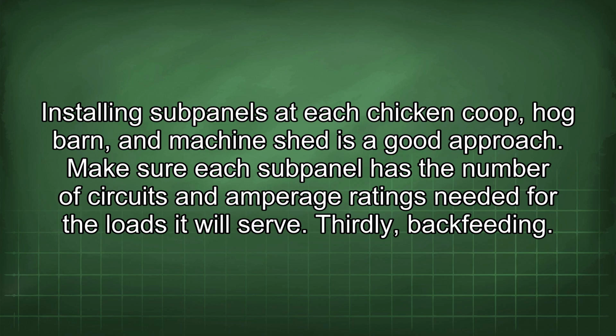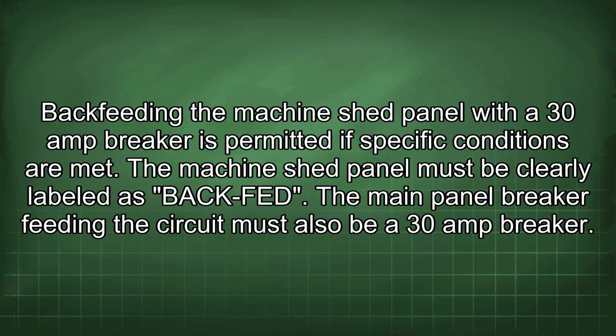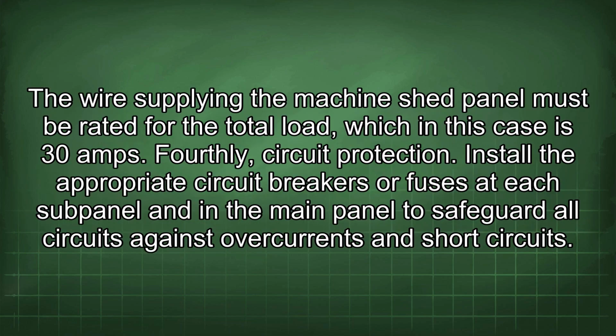Thirdly, backfeeding. Backfeeding the machine shed panel with a 30 amp breaker is permitted if specific conditions are met. The machine shed panel must be clearly labeled as back-fed. The main panel breaker feeding the circuit must also be a 30 amp breaker. The wires supplying the machine shed panel must be rated for the total load, which in this case is 30 amps.